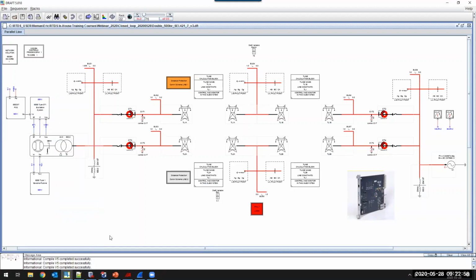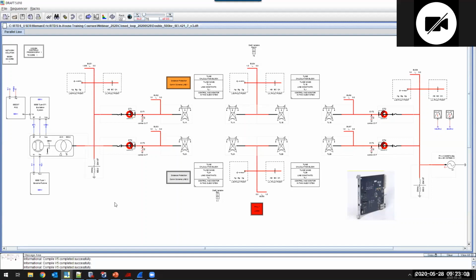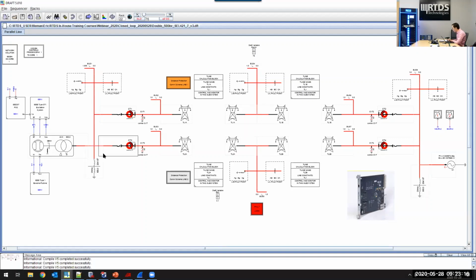Okay, so here is the simple network for the demonstration, which contains a double circuit transmission line with a generator and an infinite source at each end of the two buses. There are 4 breakers, one at each end of the terminal. The one at the right top corner here is randomly selected to be protected by an external relay, which in this demo is an SEL-421 transmission line protective relay.